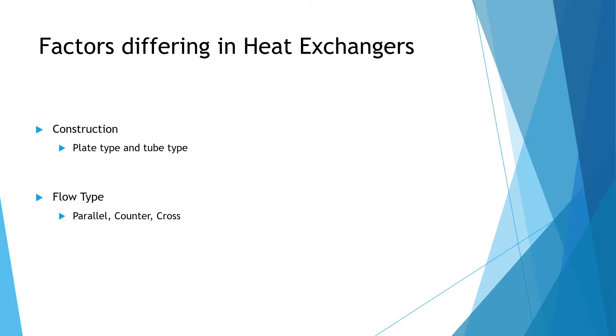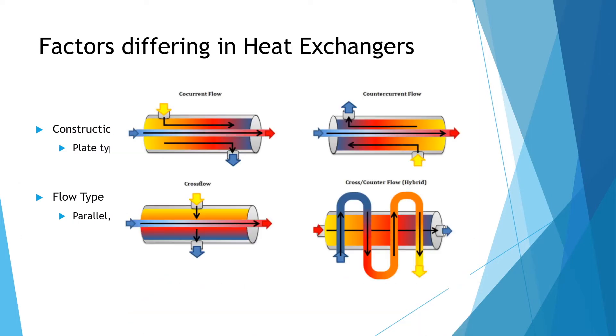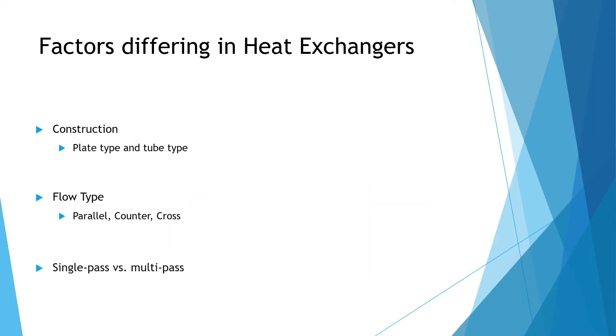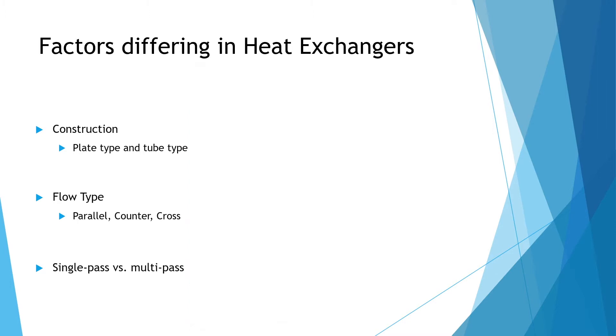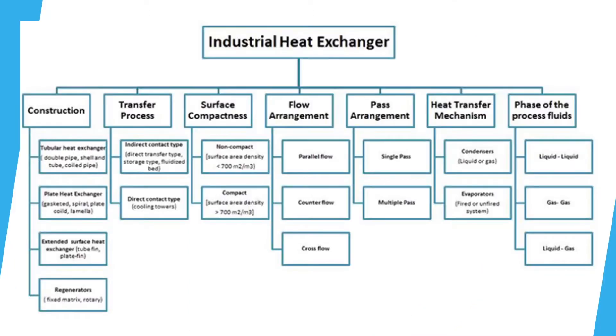Flow is another factor. Fluids may flow parallel or co-currently, which is in the same direction; they may flow counter-currently in opposite directions; or they may be cross-flow, where they flow perpendicularly to one another; or they could be a hybrid. The number of passes the flow makes also affects a heat exchanger — it can be single-pass or a multi-pass device.